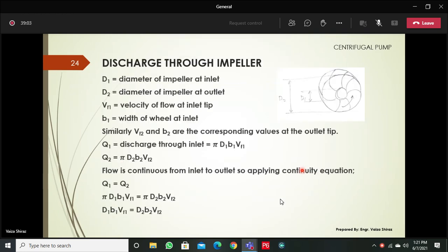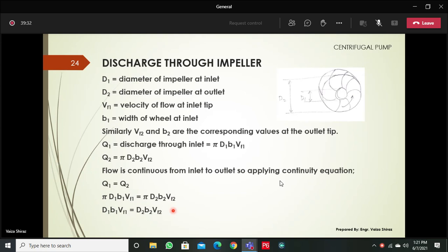To find the flow through the impeller, the equation of continuity is applied and Q1 equals Q2. Q1 is π×D1×B1×V_f1 at the inner periphery of the impeller, and Q2 is π×D2×B2×V_f2 at the outer periphery of the impeller. This equation can be used in design to find missing or unknown parameters.